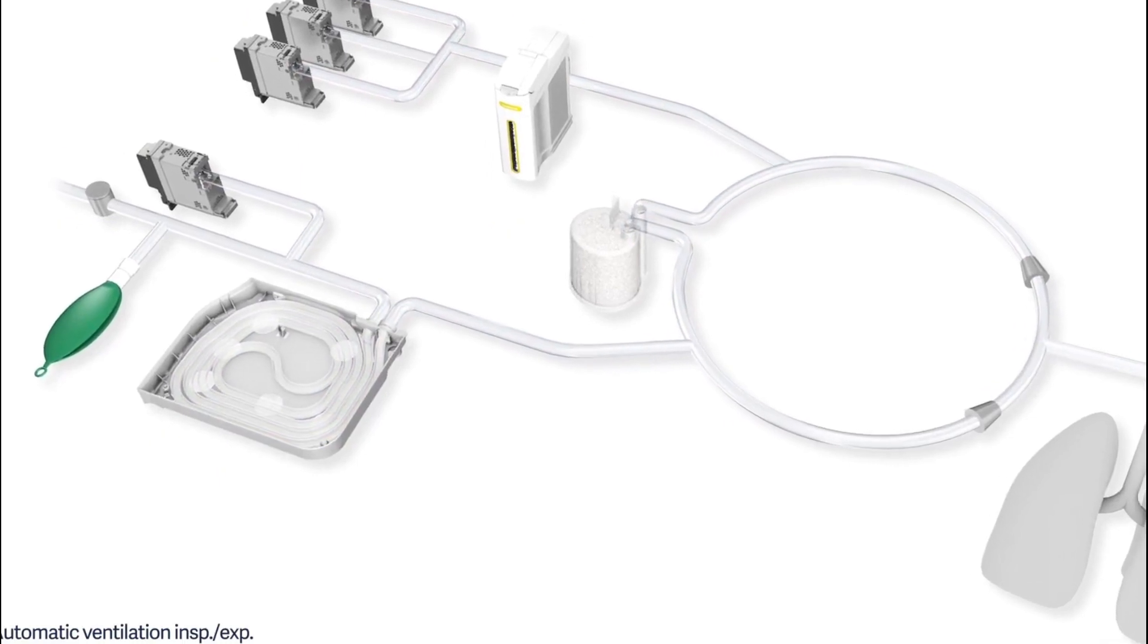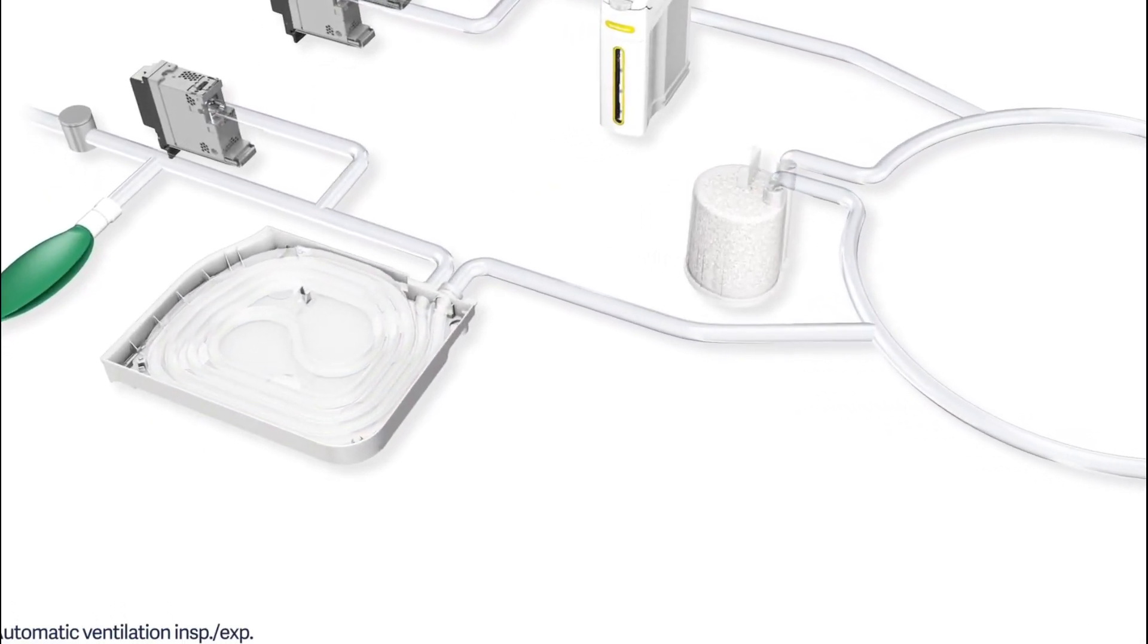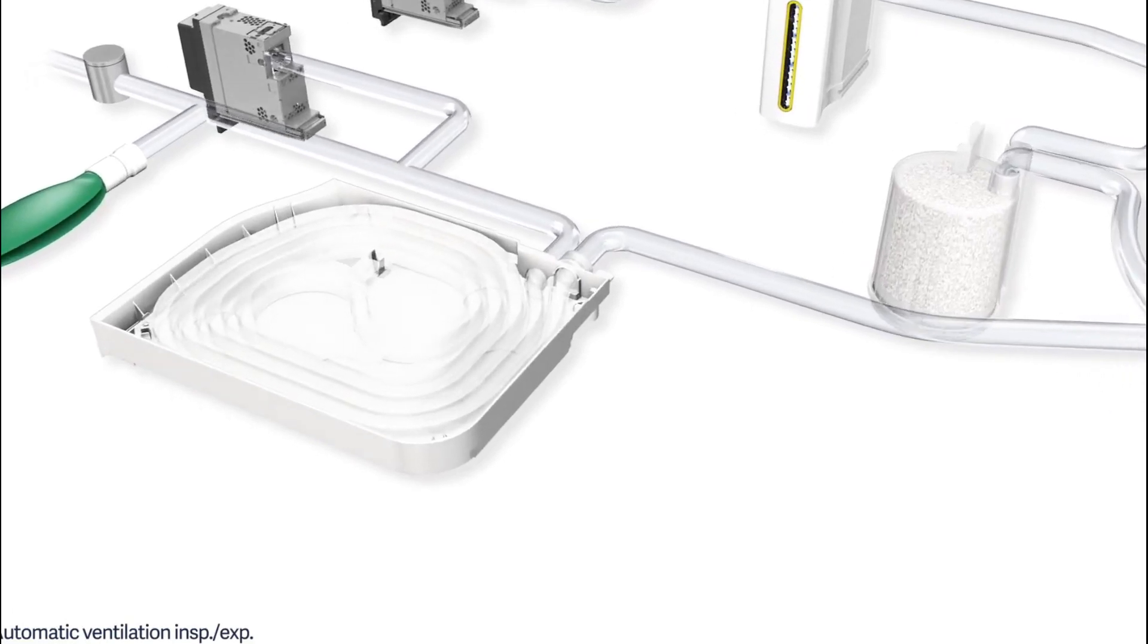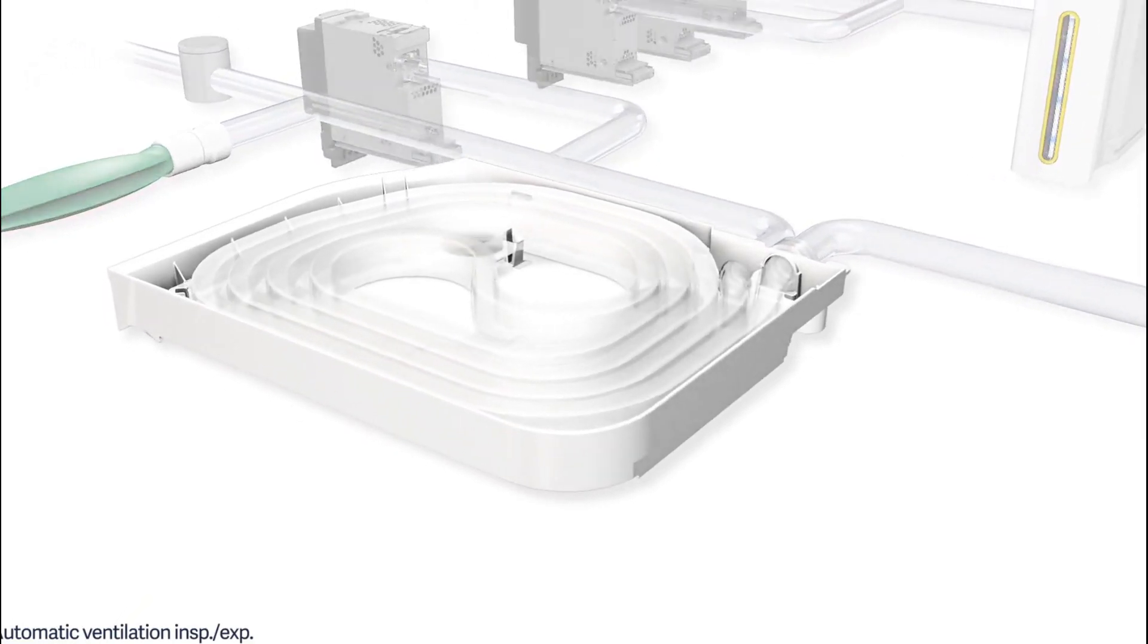Soda lime granules are described as 4 to 8 mesh, which means that each granule will fit through a mesh that has 4 openings per inch, but not one that has 8 mesh.